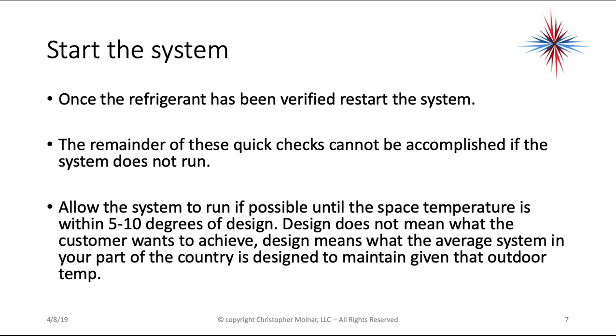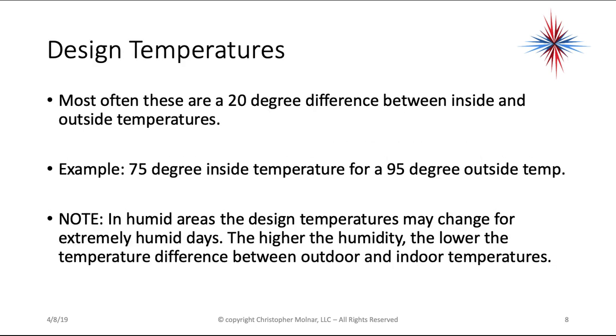Once the refrigerant has been verified, restart the system. The remainder of these quick checks cannot be accomplished if the system does not run. Allow the system to run, if possible, until the space temperature is within 5 to 10 degrees of design. Design does not mean what the customer wants to achieve — sometimes there's wishful thinking involved. Design means what the average system in your part of the country is designed to maintain given the outdoor temperature. Most often, this is a 20-degree difference between inside and outside temperatures — for example, maintaining 75°F indoors with 95°F outdoors.